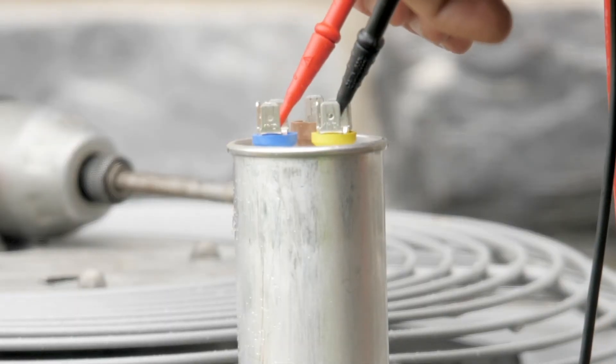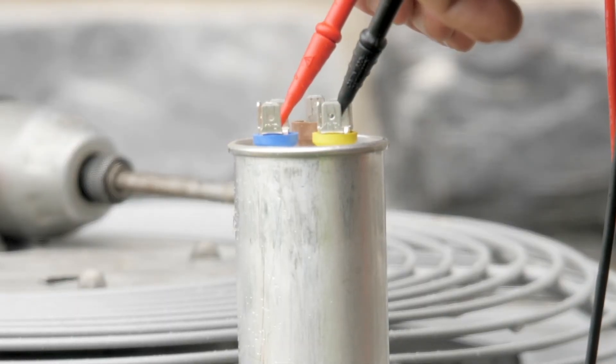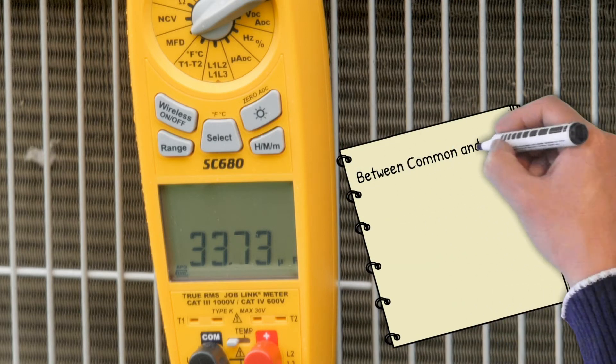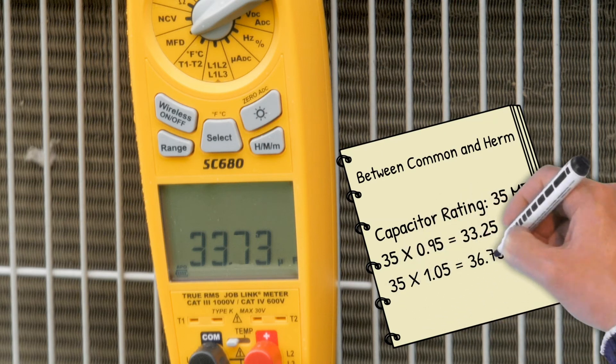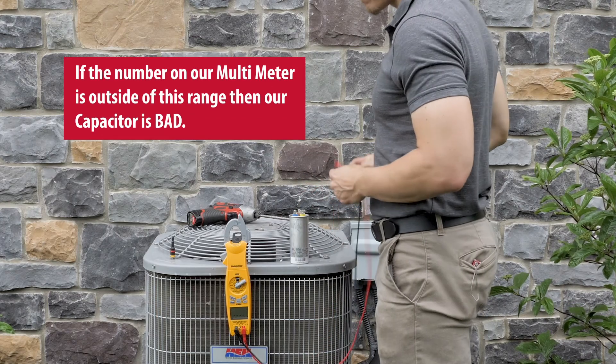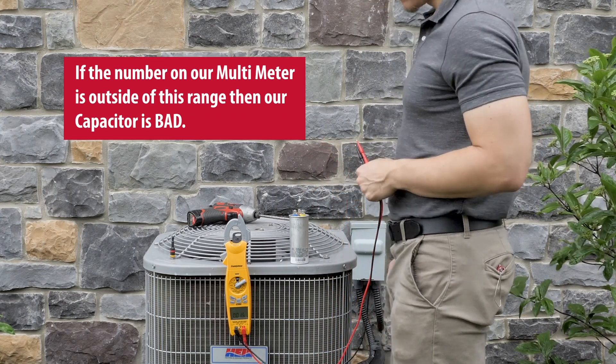Now we'll check the capacitor between the common and the Herm terminals. Again, we are multiplying our capacitor rating of 35 by 0.95 and 1.05. If the number on your meter is outside of this range, your capacitor is bad.